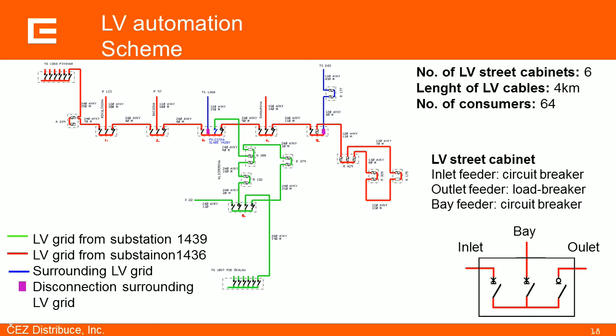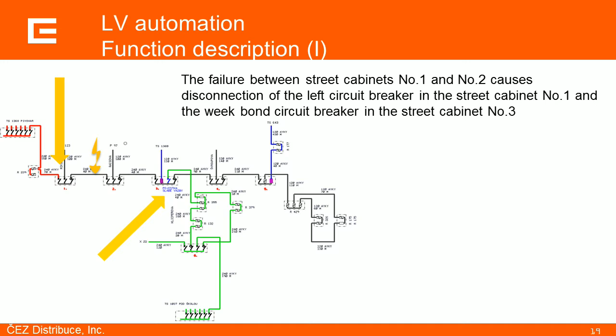So we're using remotely controlled devices in the low voltage substation to reduce the failures. If a failure occurs, for example, in the area between low voltage substation 1 and 2, then the whole part which was previously fed by the red part is without electricity supply, so now it's black. What is done in this situation is that the left circuit breaker in the first low voltage substation is disconnected, as well as the circuit breaker in substation number 3.